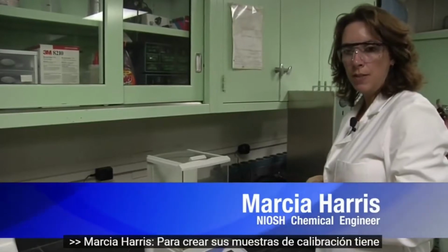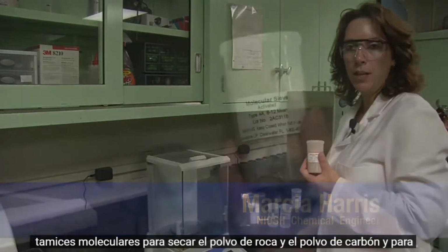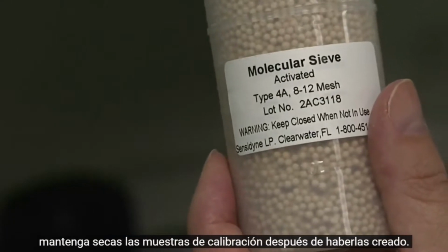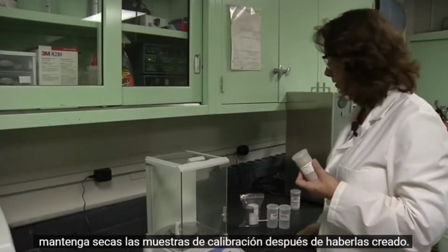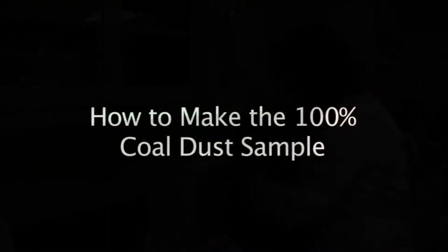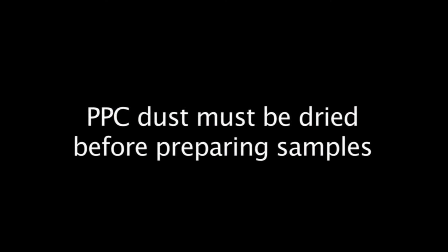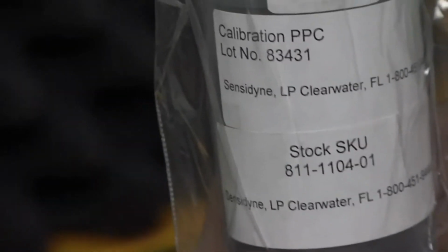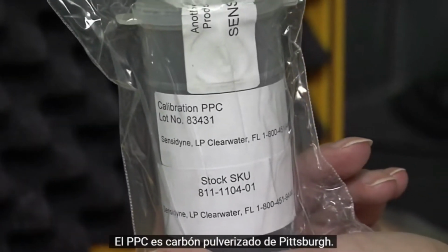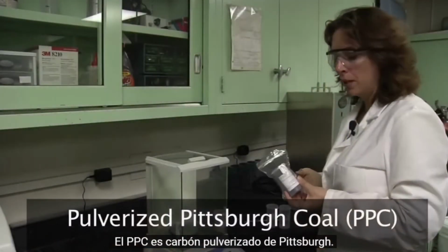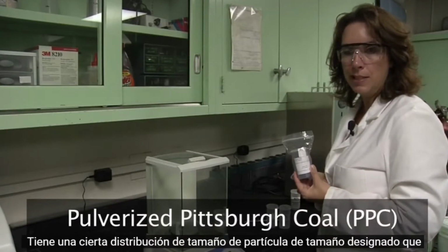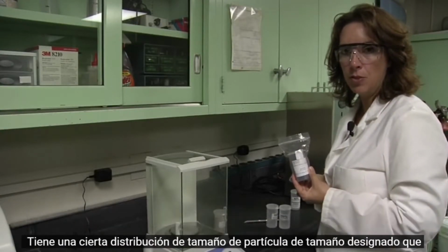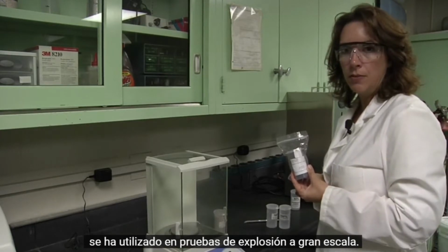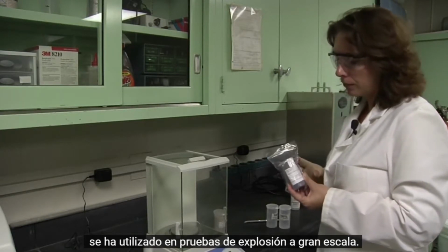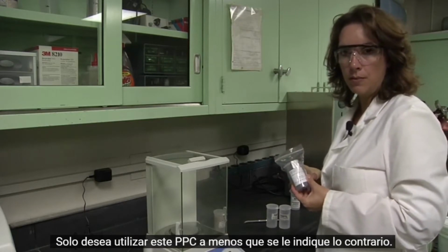To create your calibration samples, you have molecular sieves to dry your rock dust and coal dust and to keep your calibration samples dry after you've created them. Included in your kit is PPC. The PPC is pulverized Pittsburgh coal. It has a certain designated particle size distribution that has been used in full-scale explosion testing. You only want to use this PPC unless otherwise directed.